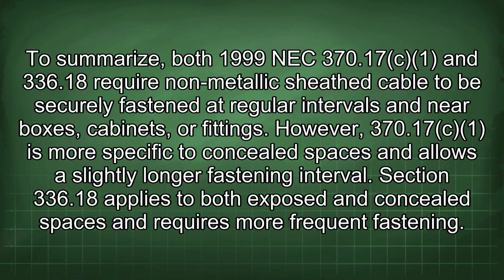To summarize, both 1999 NEC 370.17(c)(1) and 336.18 require non-metallic sheath cable to be securely fastened at regular intervals and near boxes, cabinets, or fittings. However, 370.17(c)(1) is more specific to concealed spaces and allows a slightly longer fastening interval. Section 336.18 applies to both exposed and concealed spaces and requires more frequent fastening.